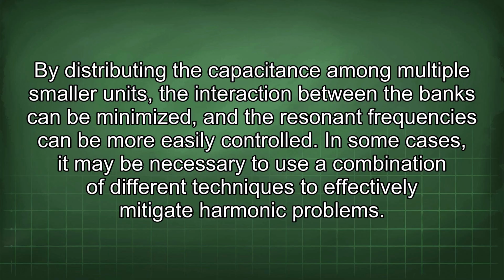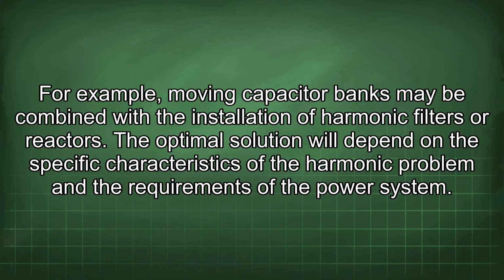In some cases, it may be necessary to use a combination of different techniques to effectively mitigate harmonic problems. For example, moving capacitor banks may be combined with the installation of harmonic filters or reactors. The optimal solution will depend on the specific characteristics of the harmonic problem and the requirements of the power system.